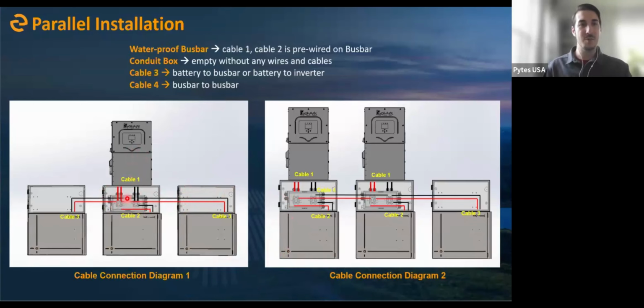The bus bar comes with cables pre-wired to land on your inverter and on one battery. We can also provide cables to attach parallel batteries to that same bus, or even attach two different bus bars together, for example if you had a higher current multi-inverter system. That bus bar is 300 amp rated, and you can use it with or without the conduit box.